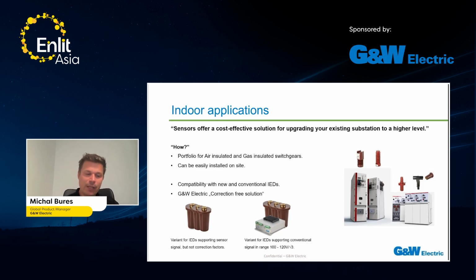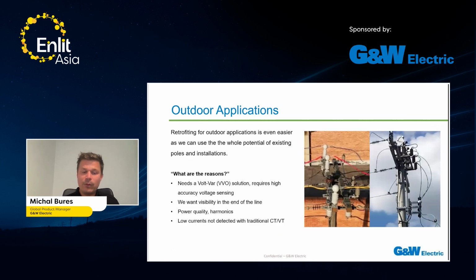For example, you can have an old IED which does not support correction factors, and you can still use the sensors. But if you have an even older IED which doesn't even support sensor inputs and accepts only VT or PT inputs, we have a package with an amplifier, which can be seen on the screen, providing a signal in the range of 100 to 120 volts. So it is very easy to connect even this sensor solution to the IED. For outdoor application, it's even easier because we just use the existing poles or installation which are already there. And we are also saving space and weight, as I already mentioned.